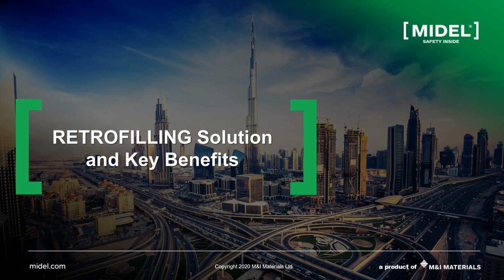It's a global picture of the transformer, and the liquid is one contributor to that. For the same transformer, we expect a hotspot temperature for a power transformer to be 7 degrees higher than that of a mineral oil, and the top oil temperature to increase by 6 degrees. Now, this is the summary. Now, to go to the application side, which is retrofilling.